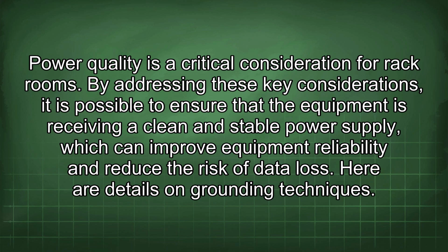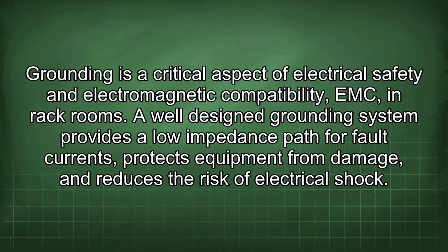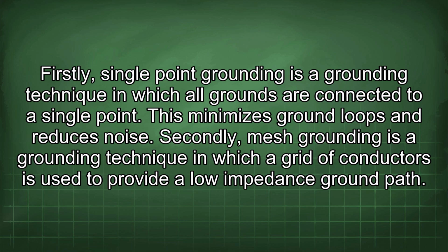Here are details on grounding techniques. Grounding is a critical aspect of electrical safety and electromagnetic compatibility in rack rooms. A well-designed grounding system provides a low impedance path for fault currents, protects equipment from damage, and reduces the risk of electrical shock. Firstly, single-point grounding is a grounding technique in which all grounds are connected to a single point. This minimizes ground loops and reduces noise.